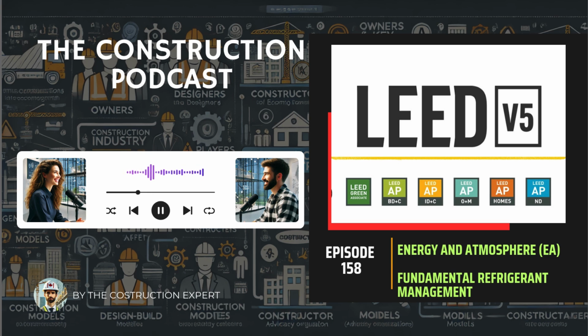Right. Number 3 is about proactive planning. Evaluate lower GWP alternatives. This happens during the design phase. If the design team is considering using any refrigerant with a GWP higher than 700, which is still quite common for some applications, they have to formally evaluate and document alternatives. The whole point is to push the design towards selecting lower impact options right from the start, whenever technically feasible. It forces the conversation about better choices early on. Okay, proactive evaluation. Makes sense.